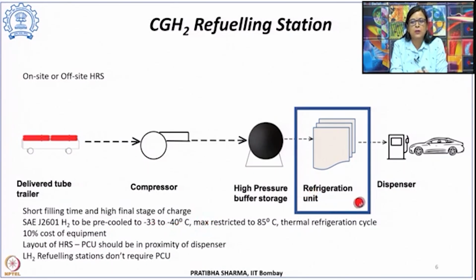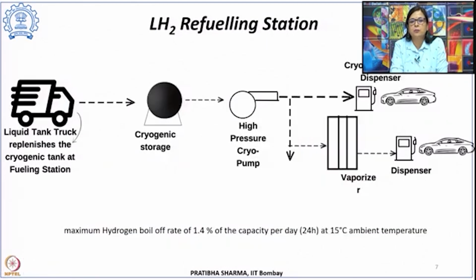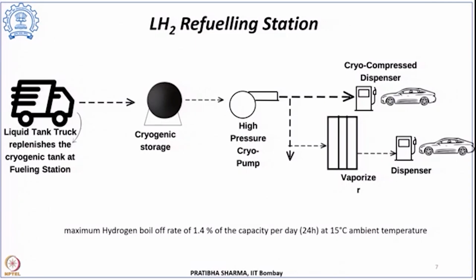Now this pre-cooling unit is cost intensive. Its equipment cost is about 10% of the total cost of the entire equipment, and it is essential while designing the hydrogen refueling station that this pre-cooling unit should be in close proximity to the dispenser. This is so as to avoid energy losses. However, this pre-cooling unit is not required if the filling station is a liquid hydrogen filling station with a cryo pump being used. So the other option could be a refueling station which operates on liquid hydrogen.